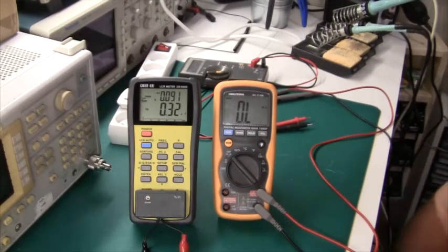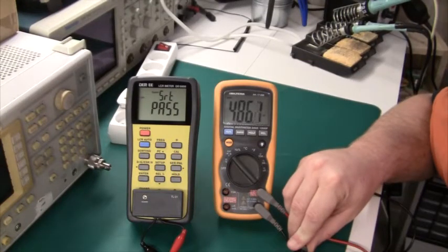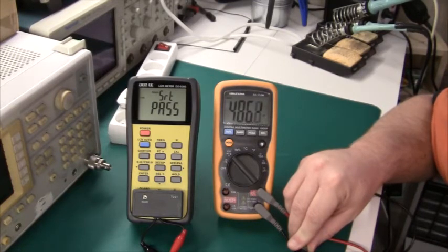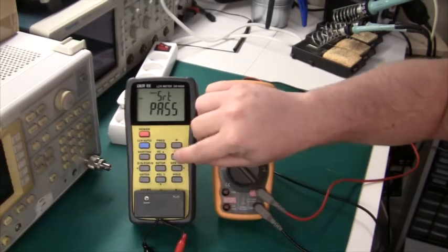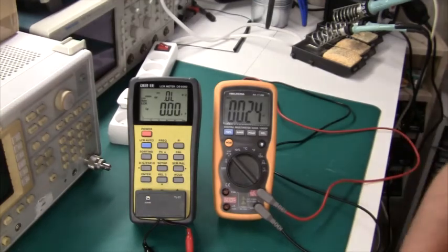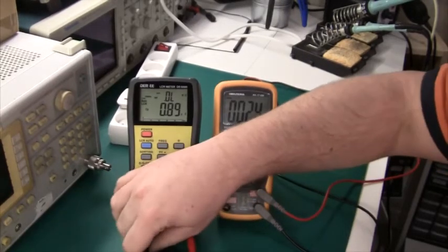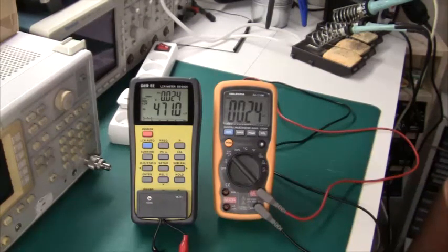The first thing I have here is a 0.47 microfarad. And my junk meter shows 486 nanofarad, which is 16 nanofarads out or roughly 4%. Now our new DE5000 is ready. Calibration is done. And it shows an open circuit. It shows 0.00 picofarad, which is amazing. Down to 3 digits. So let's plug in our 0.47 microfarad and see what it says. Yeah and it says 471, which is 0.25% out. So yeah. Nice.